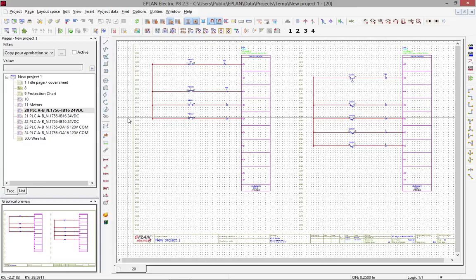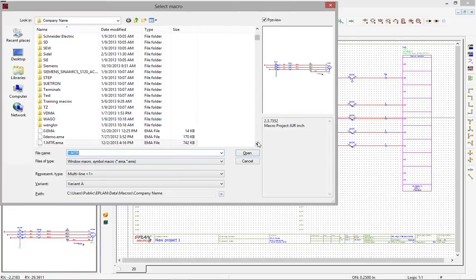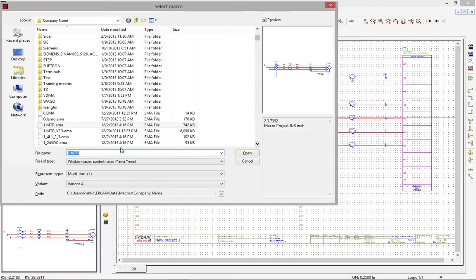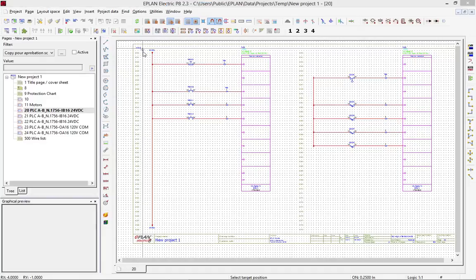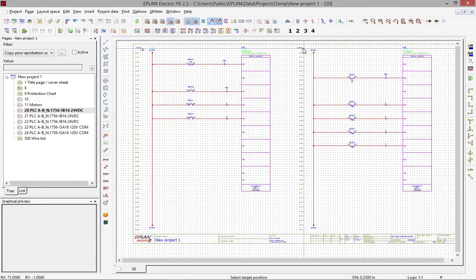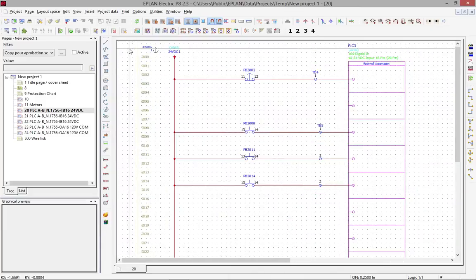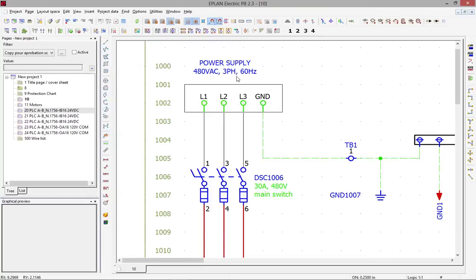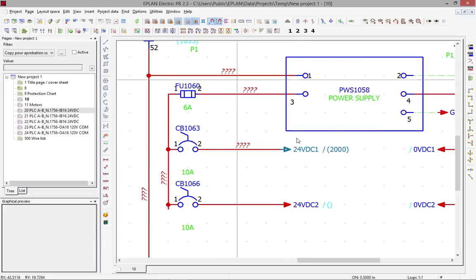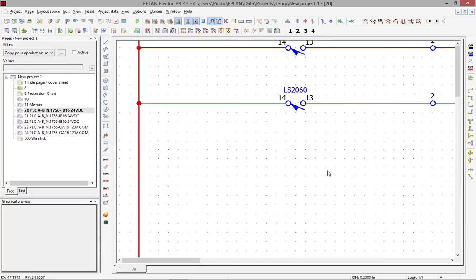Of course, I have to connect on page 20 my 24V. For this I can use one of these ePlan macros that I created. I position it wherever I need it. I say this is going to be on my circuit number 1, and this one over there will be my circuit number 2, so I just select circuit number 2. What happens at this point is the cross-reference automatically generates the cross-reference from here back to the page which contains the 24VDC1, which was my first circuit.